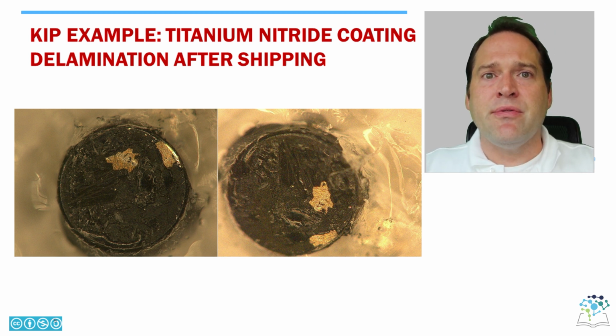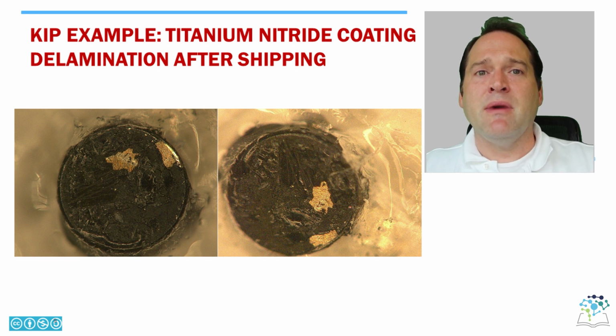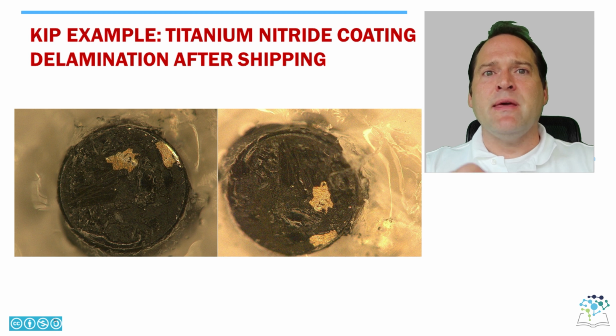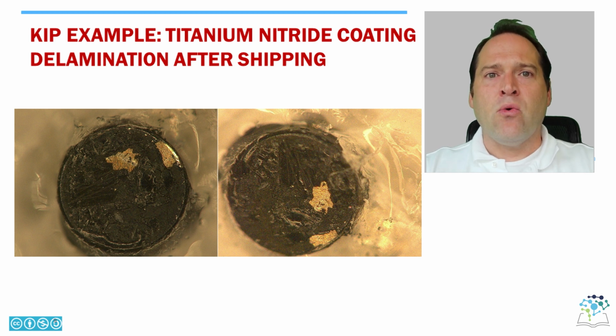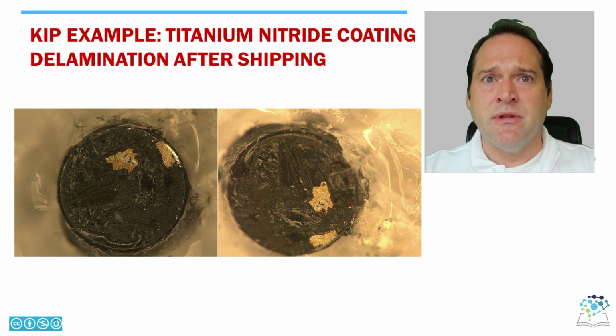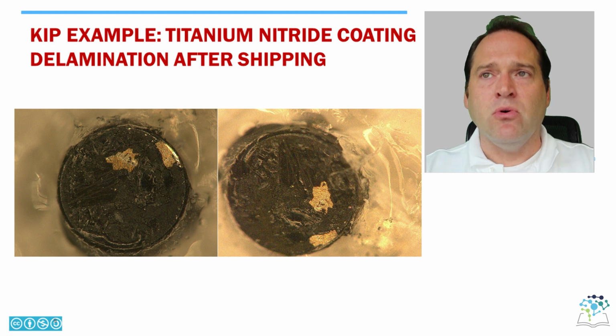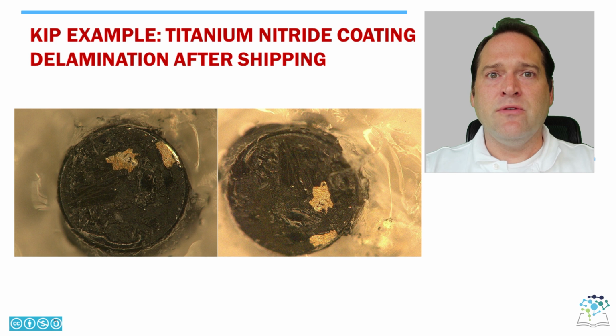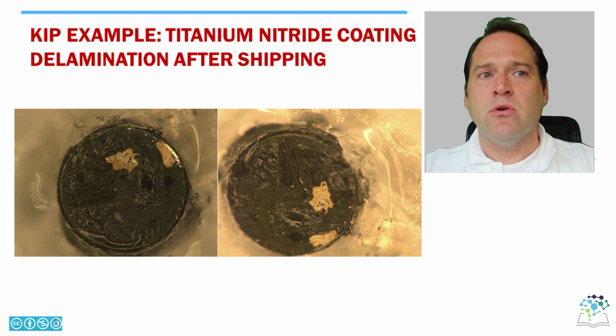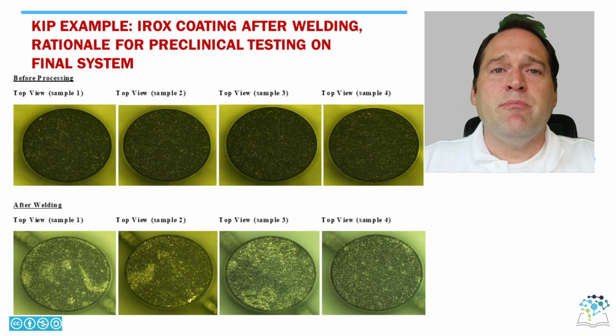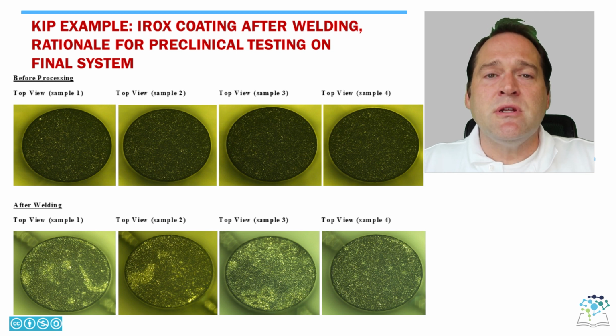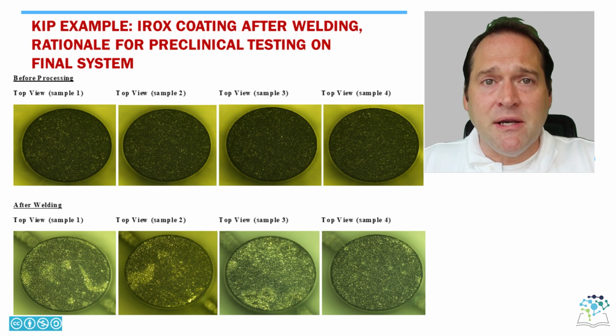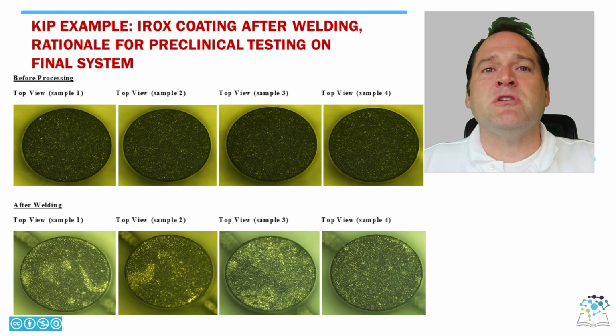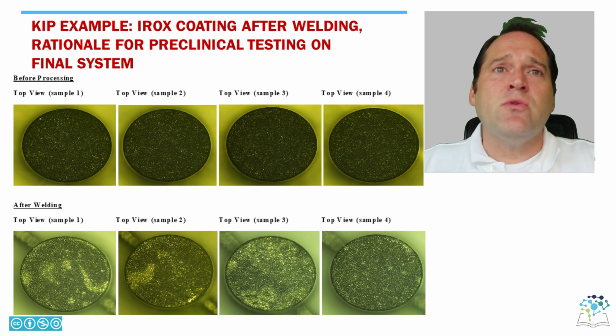And so it's really important to think through the entire process for your device, how things are being not only manufactured, but all the processes that they will go through before they arrive at the end system manufacturer, which typically is you, and you are responsible for all problems that could have happened to any module or how they might affect other components of your system. So here's another example, and this is actually a different coating that was much more robust with respect to delamination. There are certain tests you'll do for stimulation safety to test for delamination, but this is an iridium oxide coating.